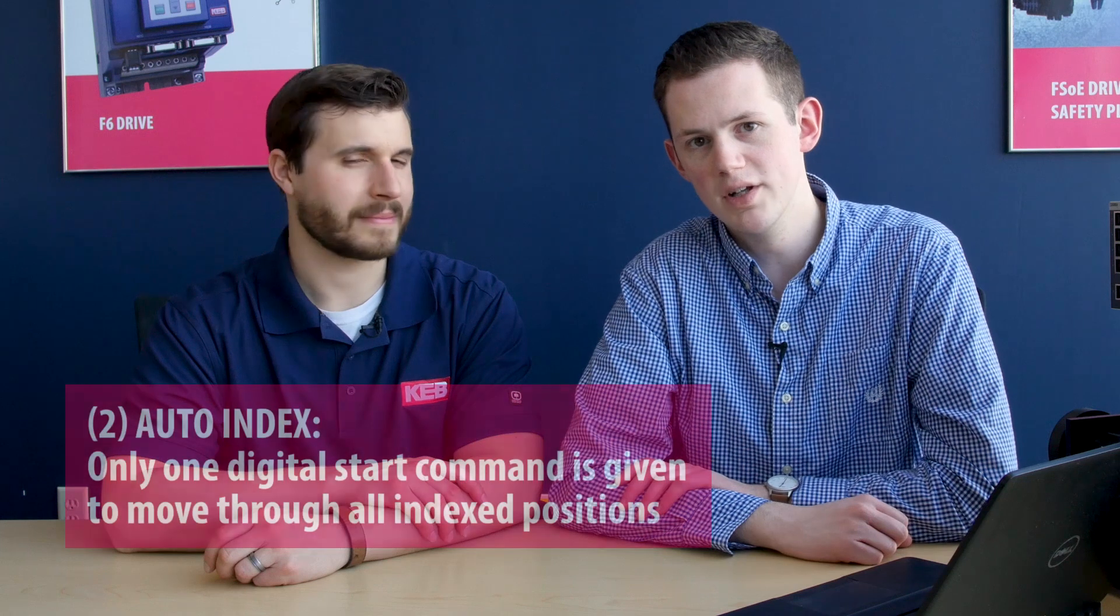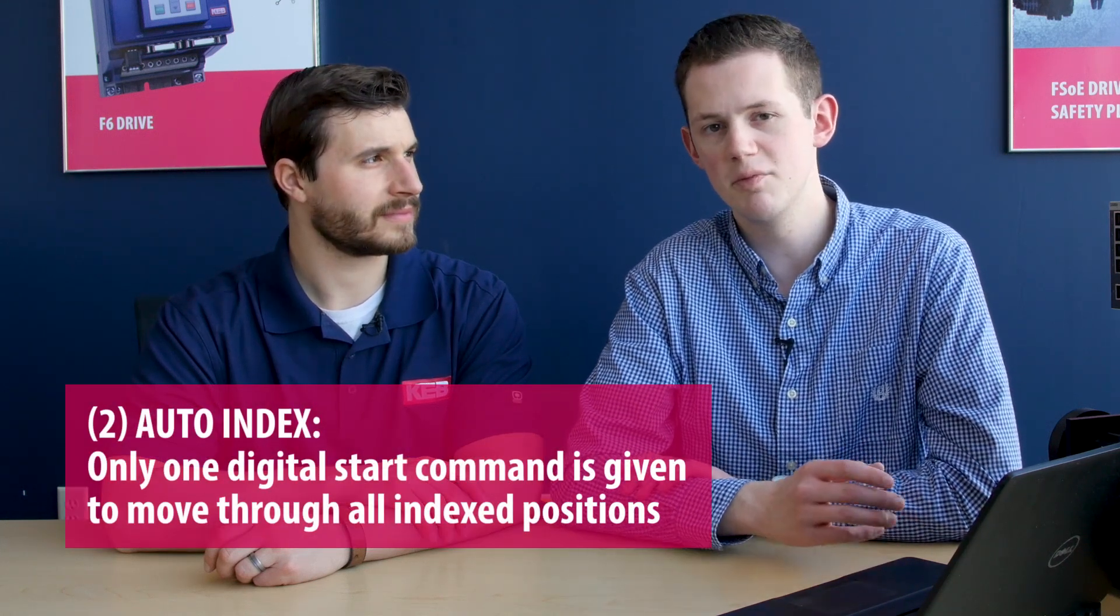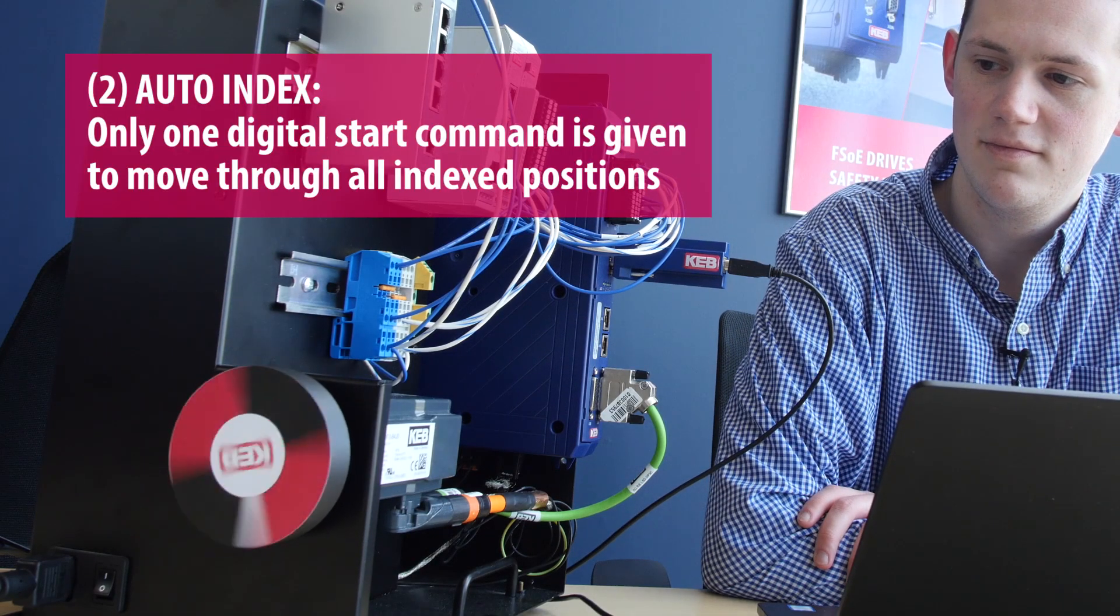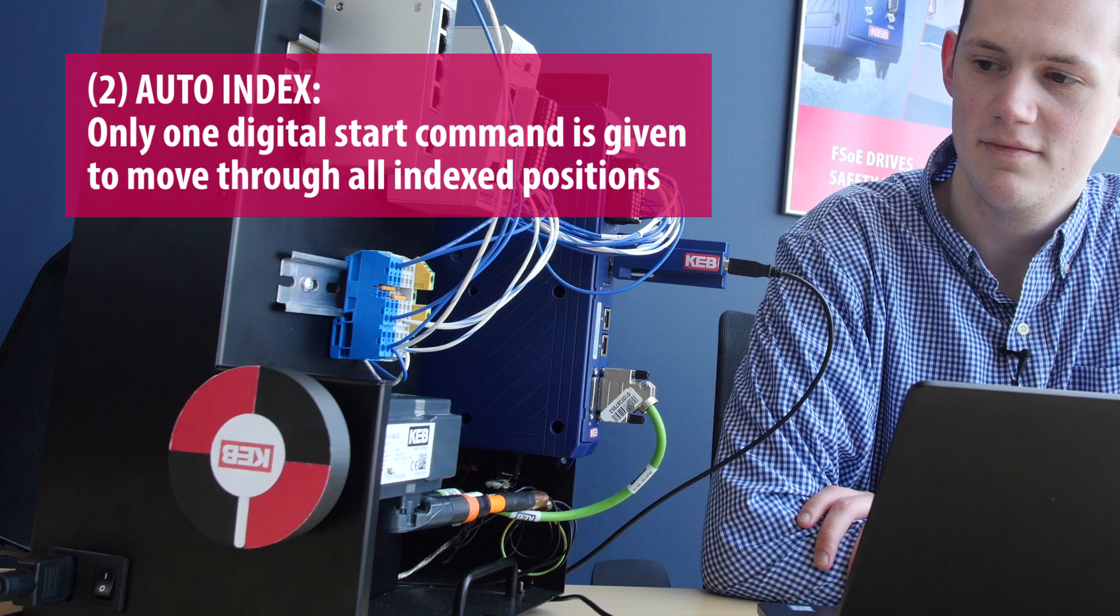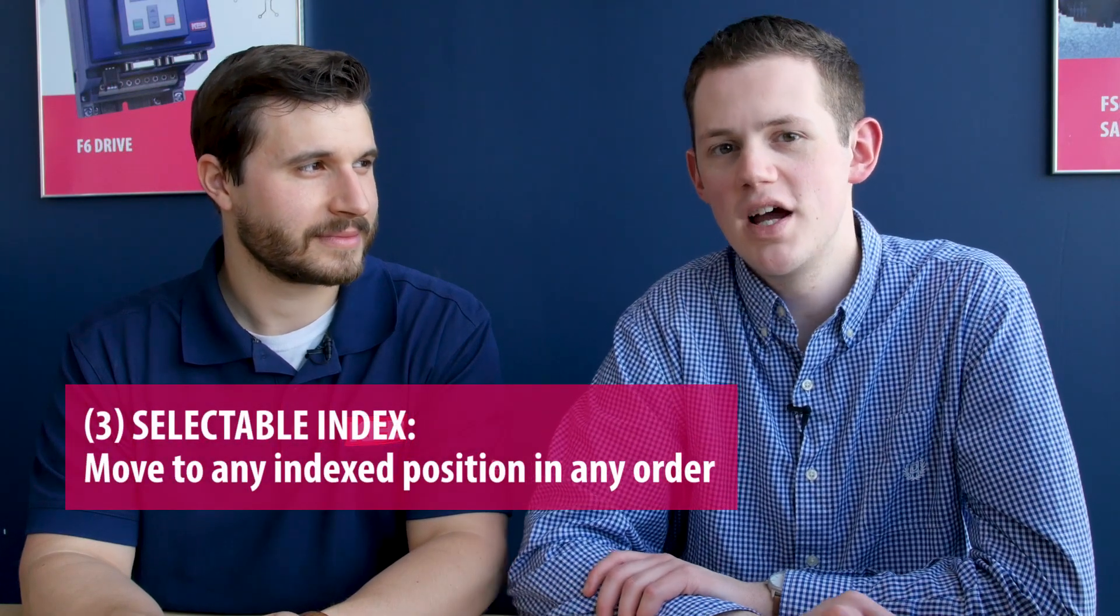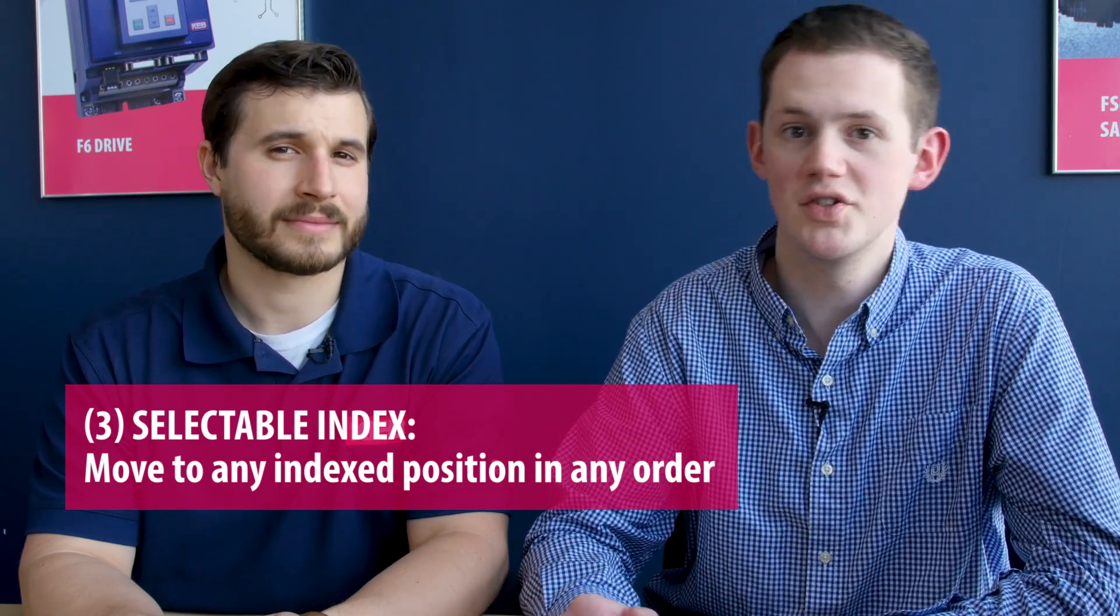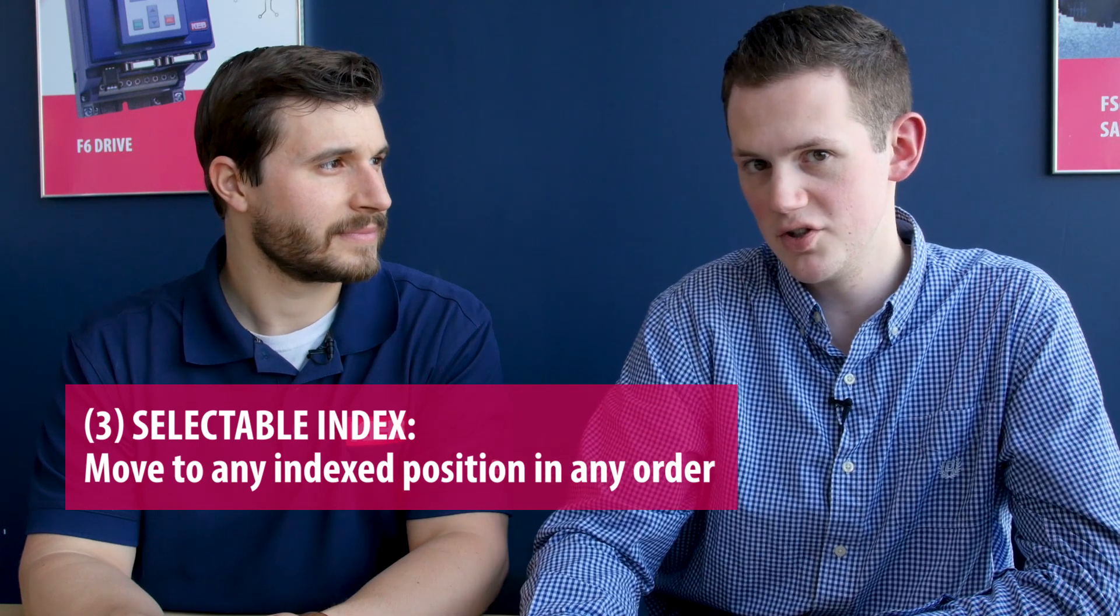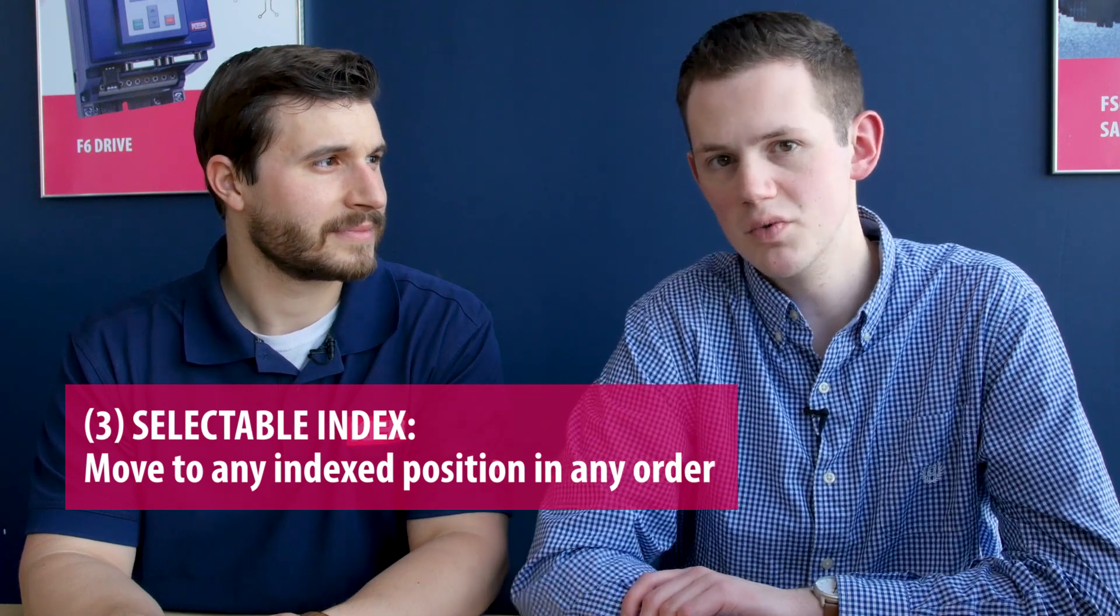The second mode is an auto index which behaves very similar to the stop after each index except requires only one positioning command at the onset of the sequence. Then the positioning module will automatically sequence through the 32 indexed positions chronologically. The third positioning mode is considered a selectable indexing mode which will allow you to select any of the 32 indexing positions in any order that you want. So you can move between position 4 and position 8 back to position 2 to position 23 to position 7 and move any order that you would like.